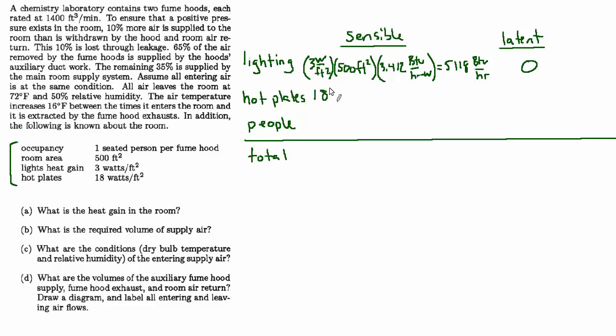So it's 18 watts per square foot times 500 square feet times 3.412 BTU per hour per watt times two-thirds, since we're going to allocate the other one-third to latent. That gives us 20,472 BTU per hour.